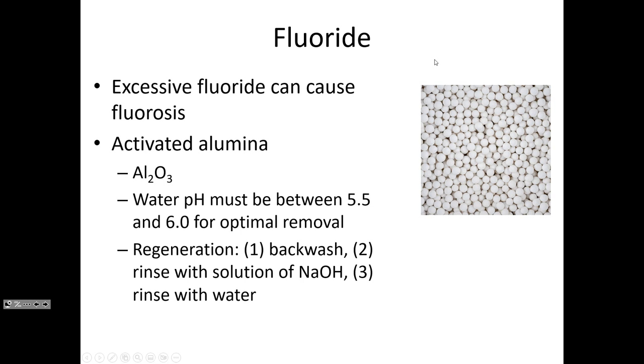Some places don't want to remove all of the fluoride — they want to leave some behind for the benefits that a moderate concentration provides. Just like ion exchange, the fluoride removal capacity of activated alumina is not infinite. There will be some clogging of the media and breakthrough, so you have to monitor the fluoride concentration in the effluent to assess the remaining capacity of the activated alumina.